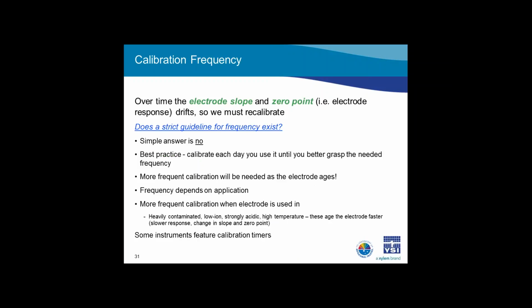A common question we are asked is, how often should I calibrate my sensor? This is probably the most difficult question we get because there is no simple answer. Calibration frequency depends on the application and the age of the electrode. Being an electrochemical sensor, a pH sensor drifts over time due to its design and how it operates. This is why we must recalibrate. Older sensors tend to drift from calibration faster than newer sensors, so older sensors will require more frequent calibrations.